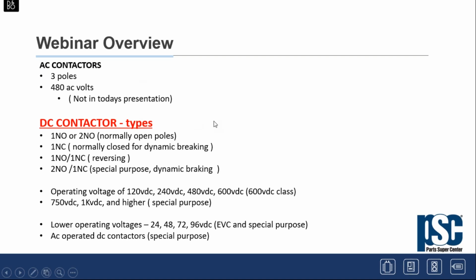At a very high level, DC contactors can either be 1 normally open, or 2 normally open power poles, or 1 normally closed power pole, primarily for dynamic braking applications. There's also 1 normally open and 1 normally closed power pole, primarily for reversing the rotation of a DC motor. Then you can have contactors with 2 normally open and 1 normally closed poles. These are more special purpose, including the normally closed contactor for dynamic braking.